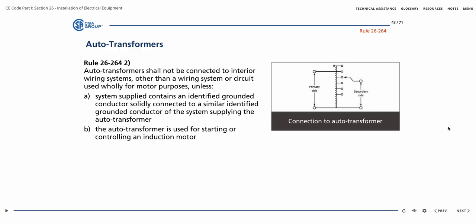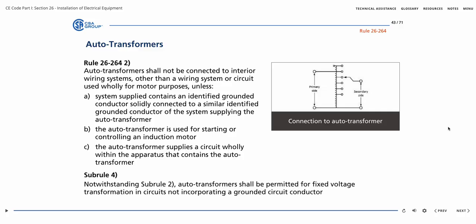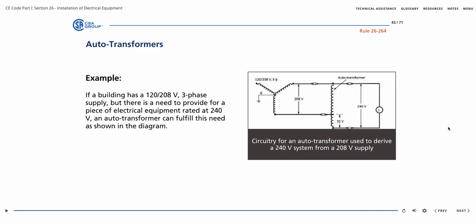The auto transformer is used for starting or controlling an induction motor, or the auto transformer supplies a circuit wholly within the apparatus that contains the auto transformer. Notwithstanding Sub-Rule 2, auto transformers shall be permitted for fixed voltage transformation in circuits not incorporating a grounded circuit conductor. For example, if a building has a 120-208 volts three-phase supply, but there is a need to provide for a piece of electrical equipment rated at 240 volts, an auto transformer can fulfill this need as shown in the diagram showing circuitry for an auto transformer.